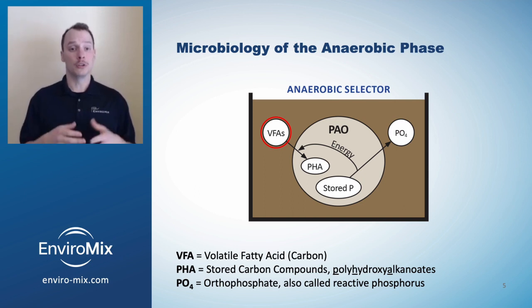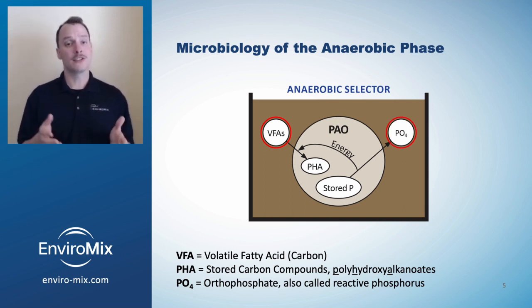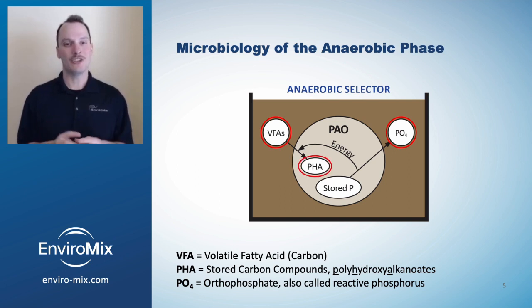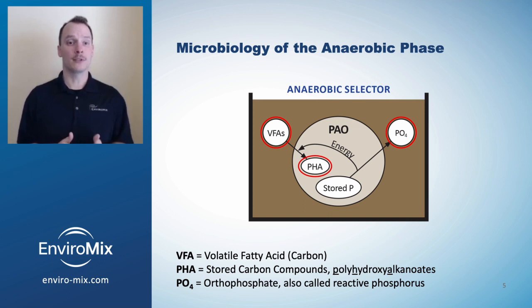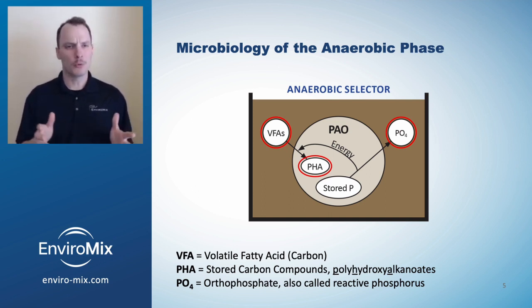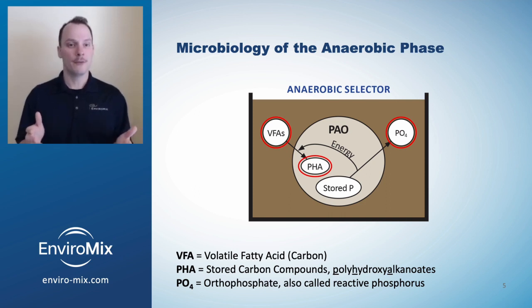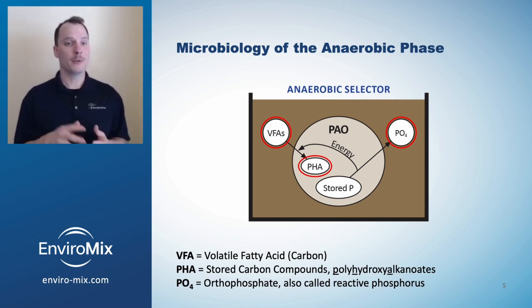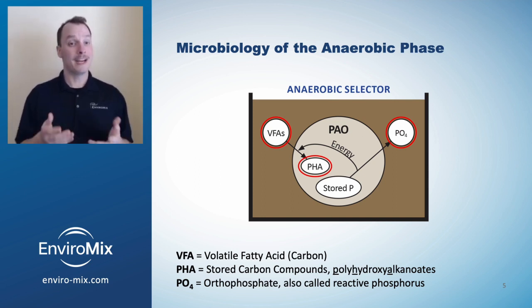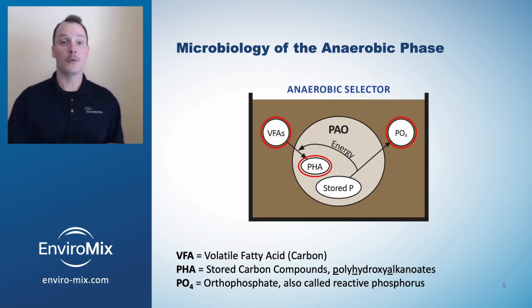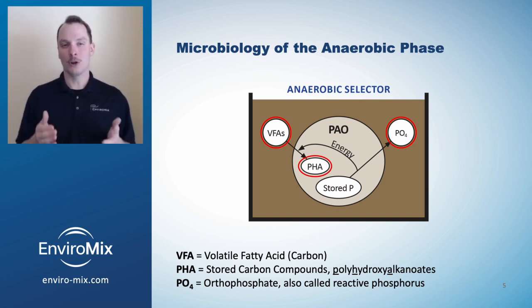The PAOs release phosphorus and convert and store carbon within the cell as compounds called PHAs. You may notice that this step actually releases more phosphorus into the wastewater, and you would not be alone in thinking: if we want to remove phosphorus, why are we letting the microbes release it? But what's important to understand with this phase is that the anaerobic environment gives PAOs a competitive advantage to grow that they wouldn't otherwise have with aerobic treatment alone.